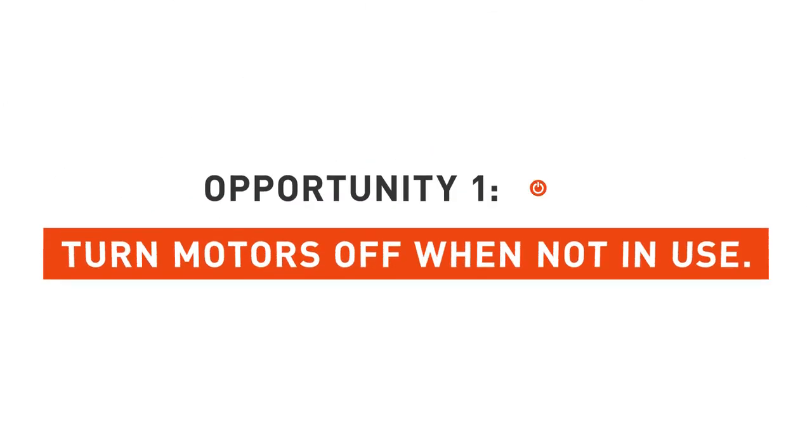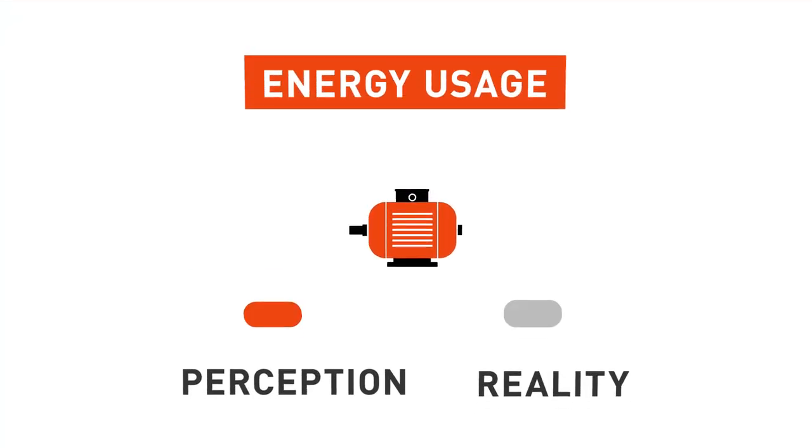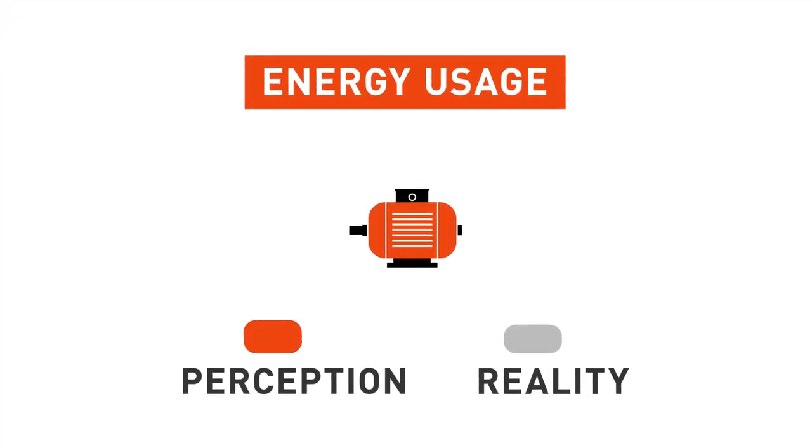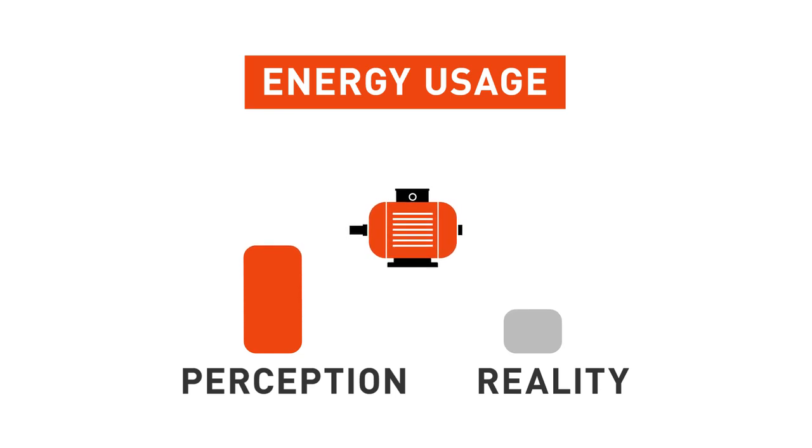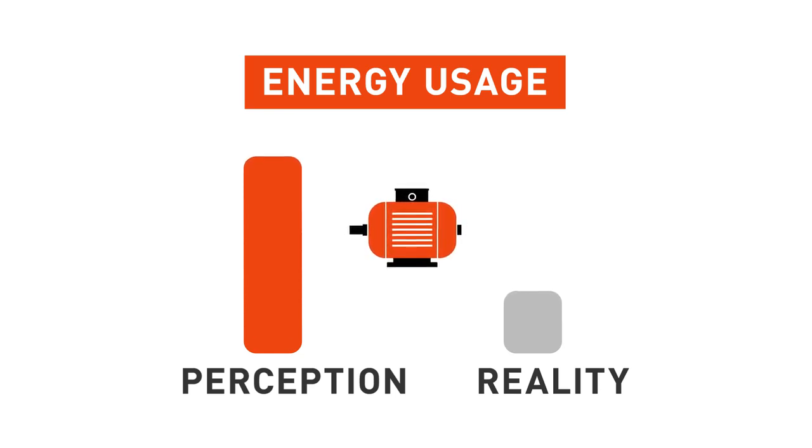The biggest opportunity for motors is to turn them off where they're not being used. There's a perception that it costs a lot of extra energy to turn a motor on, so they tend to be left on over breaks. You have to look very carefully at that. There is a slight bump in energy increase when you turn a motor on, but it's usually a lot smaller than what most people see.